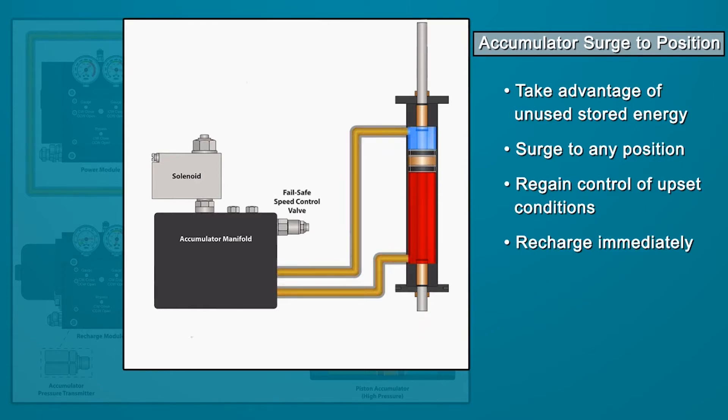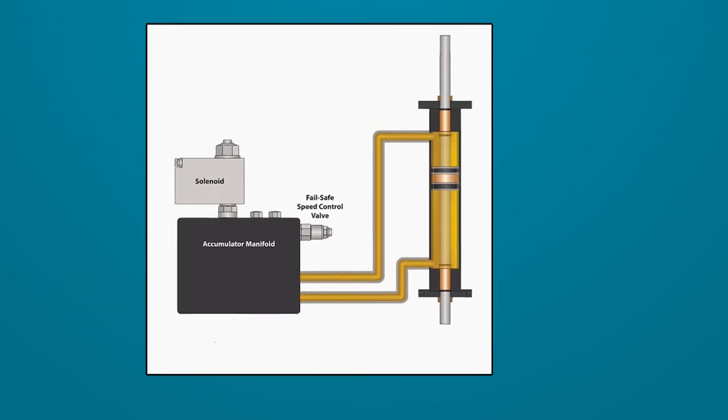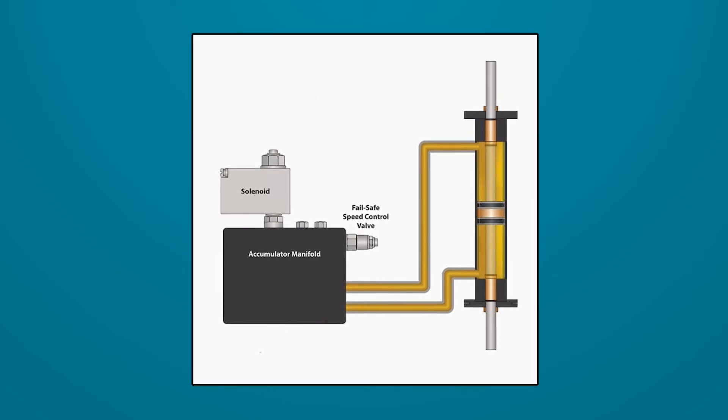This surge capability takes advantage of stored energy for large and fast step changes beyond the speed capability of the actuator's standard power module. When an upset condition requires a large step change, the quickest way to reach the new target position and get the process under control is through an accumulator surge.